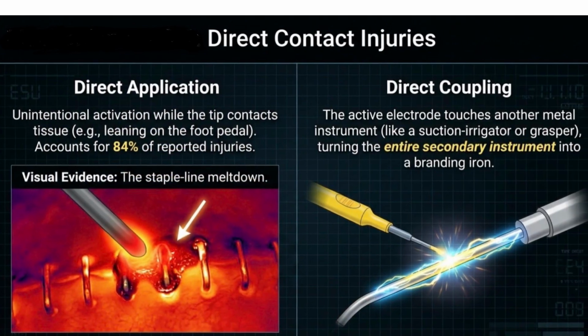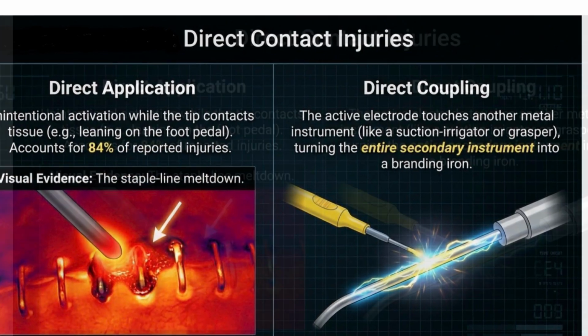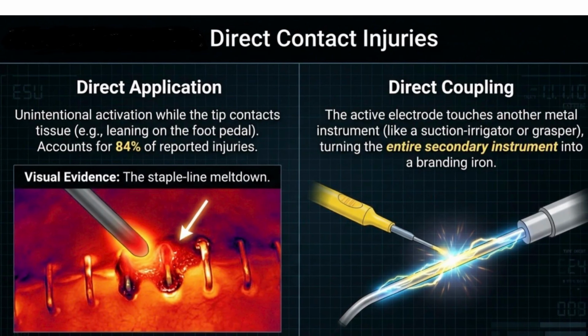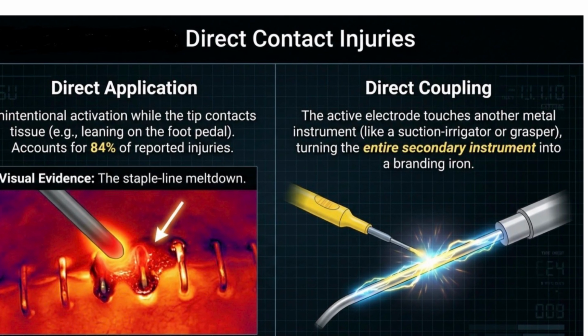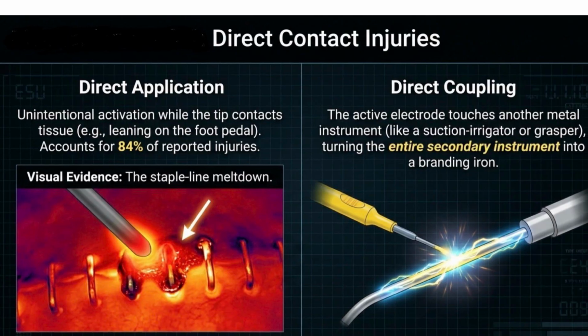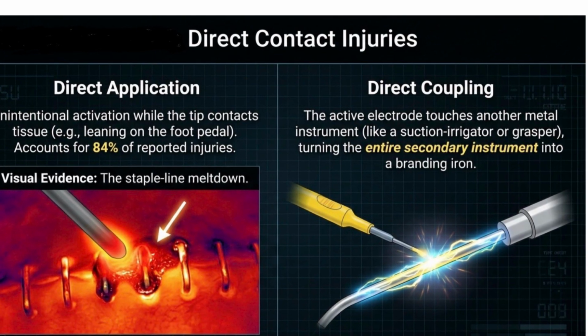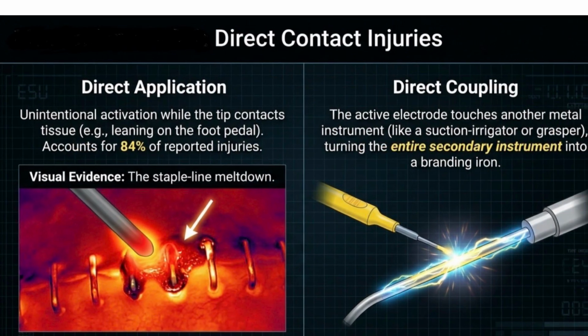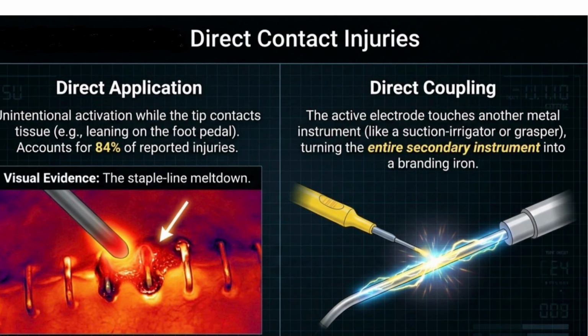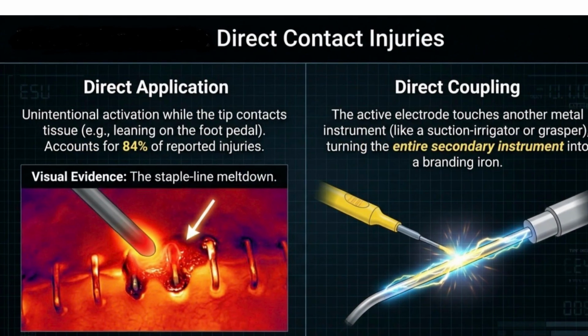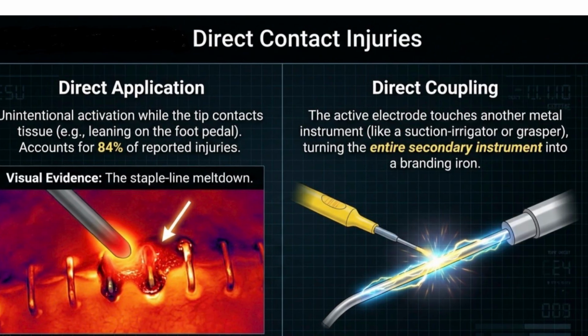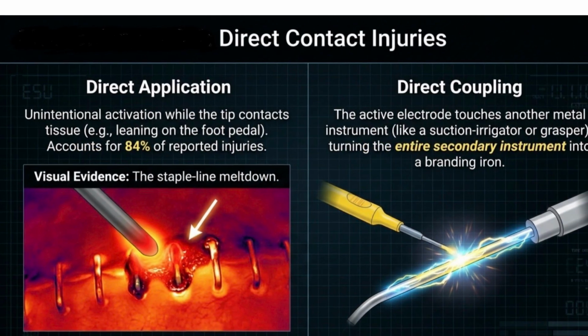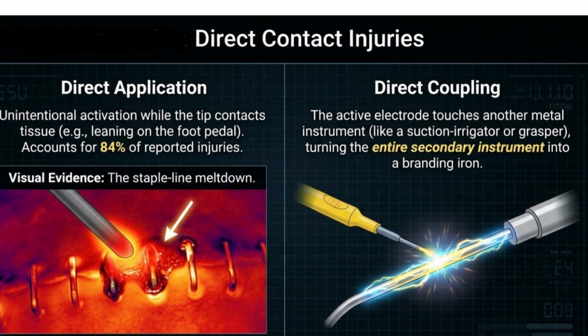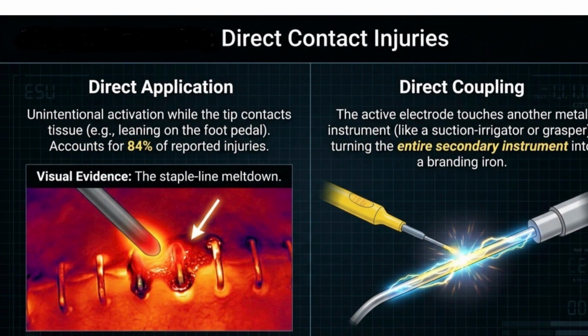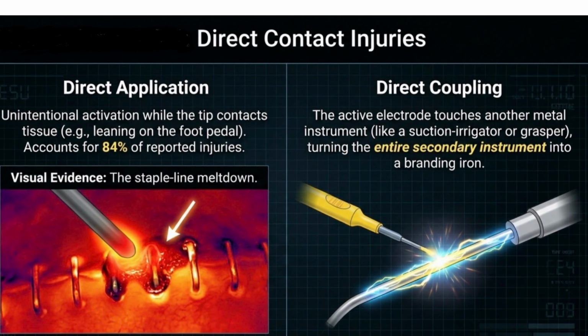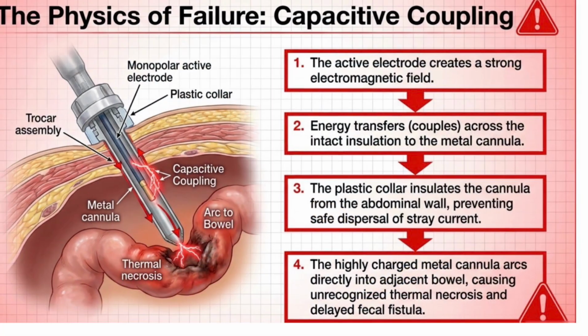Direct contact injuries happen by direct application or through direct coupling. Unintentional activation while the tip contacts tissue happens on leaning forward onto the foot pedal and accounts for 85% of reported injuries. In direct coupling, the active electrode touches another metal instrument like a suction irrigation or a grasper, turning the entire secondary instrument into a branding iron.